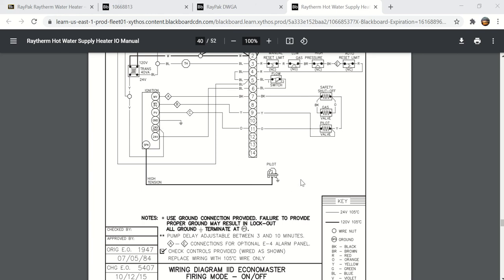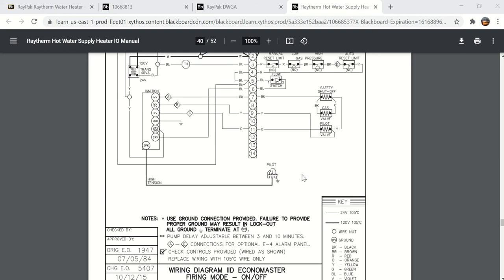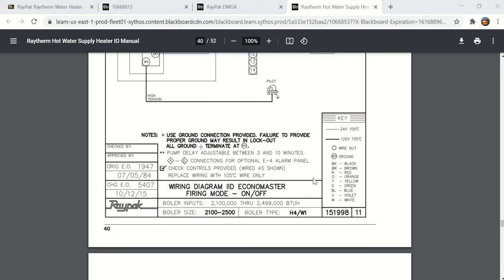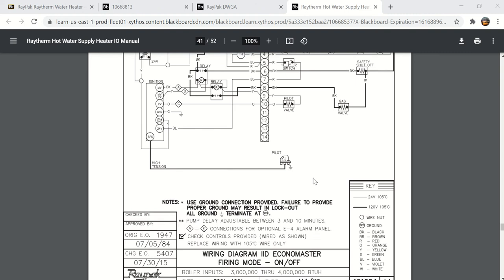That's probably the biggest thing that causes ignition failures on this type of ignition control, is that you don't get a good ground from the pilot assembly to the ignition module. And if you don't have a good ground there, or an actual physical wire that goes from this point to this point, then you're not going to get a good flame signal reading, and that would cause you to have an intermittent flame failure problem.